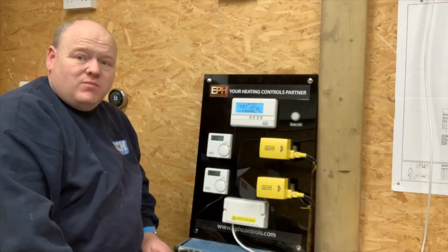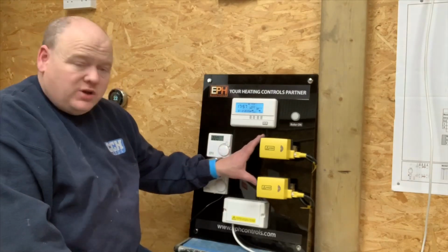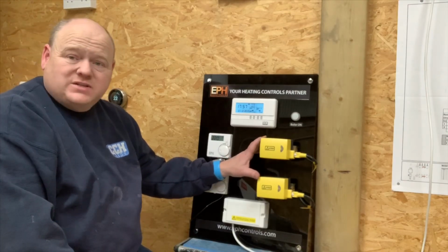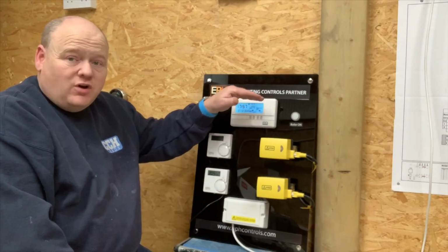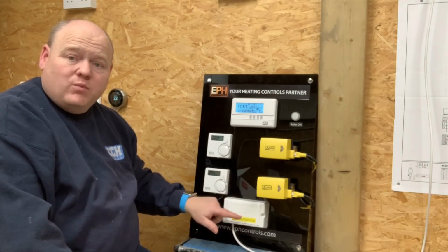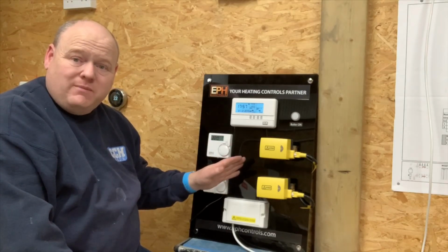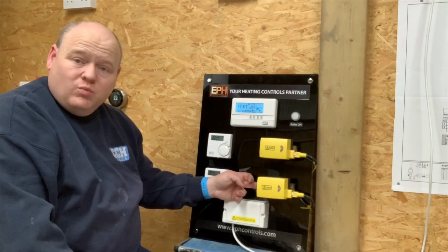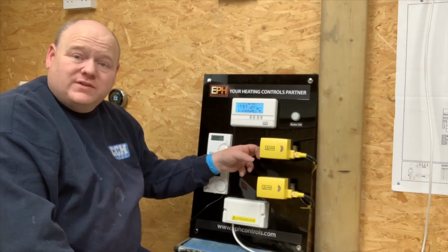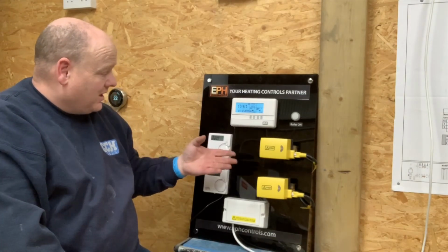The S plan system works in a very similar way to a Y plan system, but you have two valves instead of one valve. Or if it was an S plan plus, you might have 3 valves or 4 or 5 or whatever. And how that would work, you'd have your flow pipe come up from the boiler, and then it would T. So you'd have a T pipe in it, and one part of it would go to one valve and the other would go to the other valve, and then you may also have another T that would go to a bypass as well.